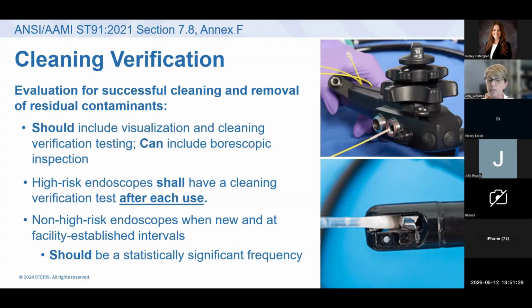High-risk endoscopes, the guidelines say they shall be monitored with cleaning verification after each cleaning, after each use. So the 6 categories I mentioned in the beginning: cystoscopes, duodenoscopes, ureteroscopes, bronchoscopes, EUS and EBUS. They should have cleaning verification testing performed every time they are reprocessed. So if you're doing protein, carb, ATP, whatever, that should be performed on those categories every time they're cleaned.